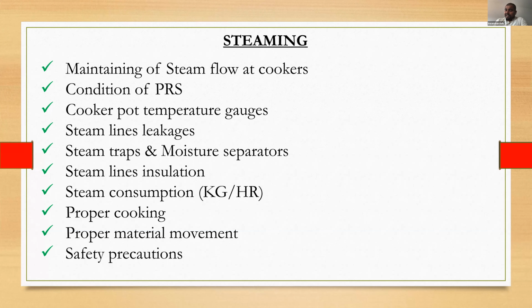Every 25 to 30 meters we have to put a trap and moisture separator, which will reduce the condensation. And if you put insulation on the steam lines, that's the next point, steam line insulation. If you put insulation, these losses will not happen, and the steam will be very high efficiency, like saturated steam and all.